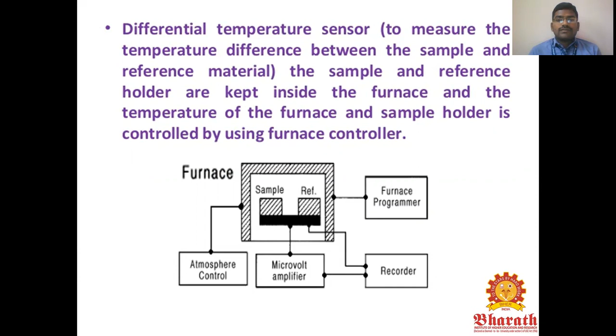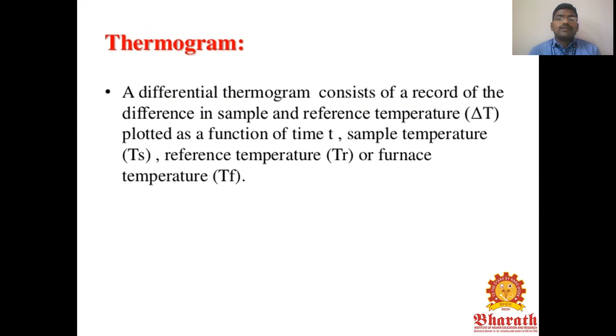Another is the microvolt amplifier. Next is the recorder, the thermogram. The differential thermogram consists of a record of the difference between the sample and reference temperature, delta T, plotted as a function of time t, sample temperature Ts, reference temperature Tr, and furnace temperature Tf. At that time you have to draw the thermogram. This is one of the thermograms. The peak at the bottom is the endothermic reaction, while oxidative reaction is possible for exothermic reaction, where heat is released.